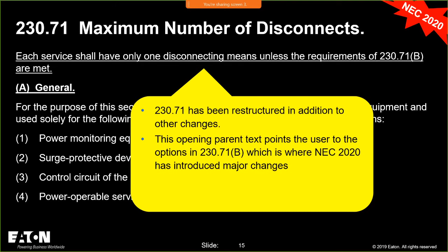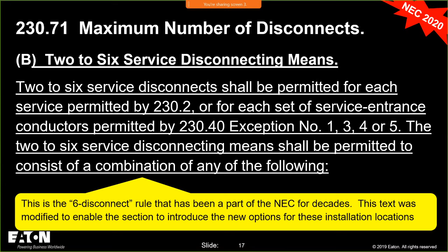So this says 2 to 6 service disconnects shall be permitted for each service permitted by 230.2, for each set of service entrance conductors permitted by 230.40, those exceptions. 2 to 6 service disconnecting means shall be permitted to consist of a combination of any of the following. So what they did was they gave us a recipe. And again, this is what I refer to as the 6 disconnect rule. They now gave us a recipe of 4 options that we can use.